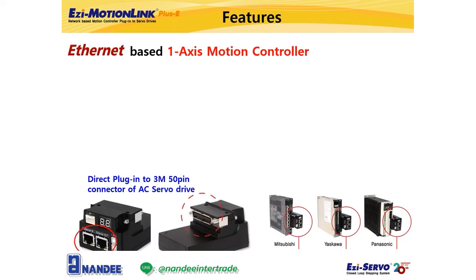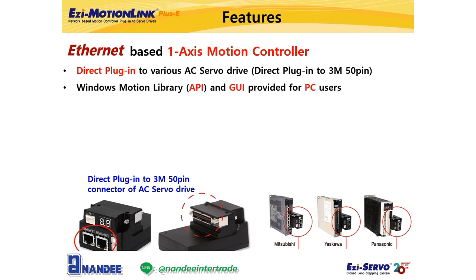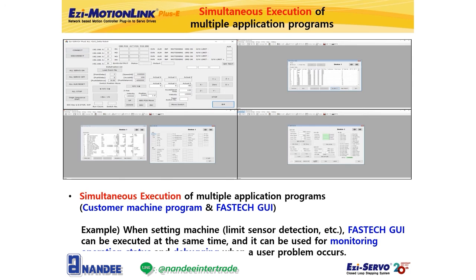Let's summarize the features of EZMotionLink. EZMotionLink Plus E is an Ethernet-based one-axis motion controller for AC servo. It can be used by plugging it into the interface connector of the AC servo drive. Since most AC servo drives use the 3M 50-pin connector, you can easily connect EZMotionLink to various AC servo drives such as Mitsubishi, Yaskawa, and Panasonic. Windows-based API and GUI are provided for PC users. You can run multiple applications at the same time — for instance, monitoring parameter values, I/O status, position values, speed values, etc. using our GUI program even when the customer's machine program is running. For example, you can check whether the limit sensor works properly during machine setting by running our GUI at the same time.